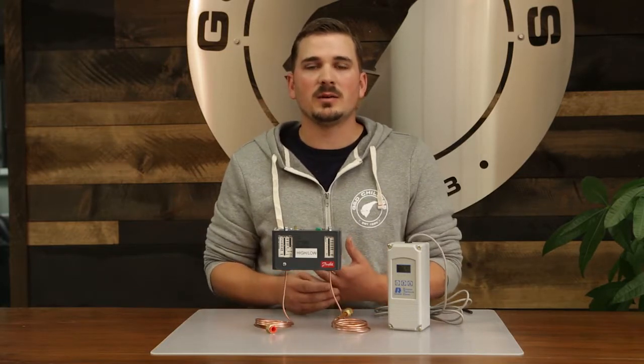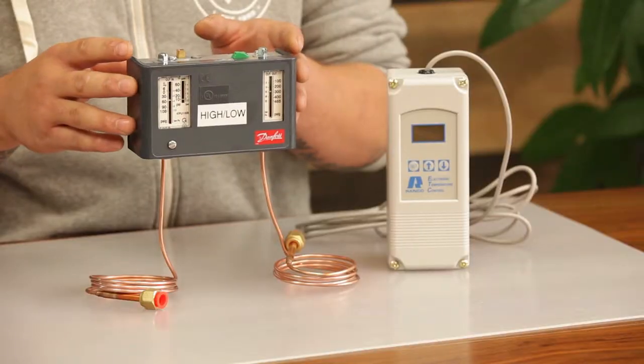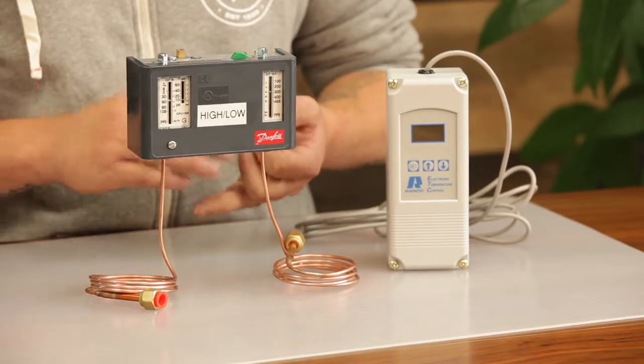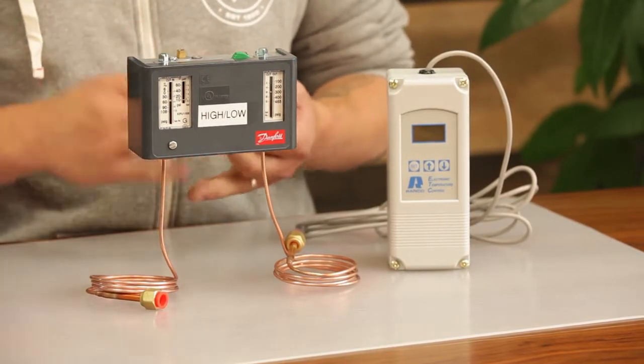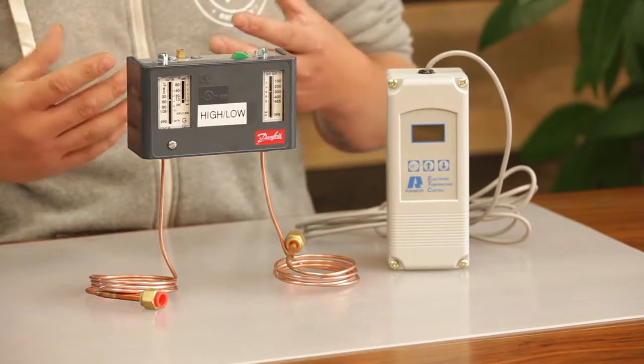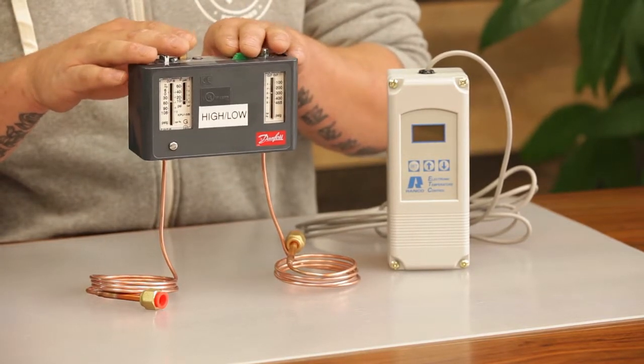One of the areas that can come into play is this high-low switch. If the pressures get too high due to lack of airflow or too hot of weather, air being pulled in through the condenser, the pressures are going to rise in the machine and this switch is going to trip. It's a safety to protect that.